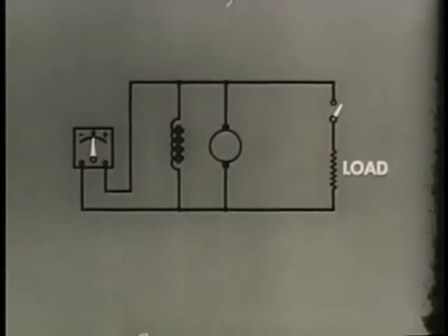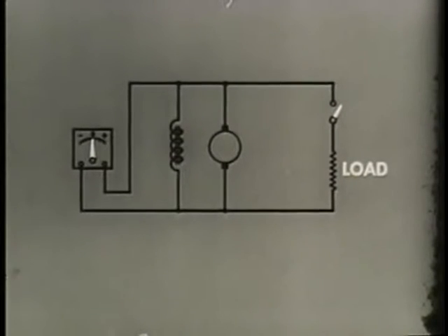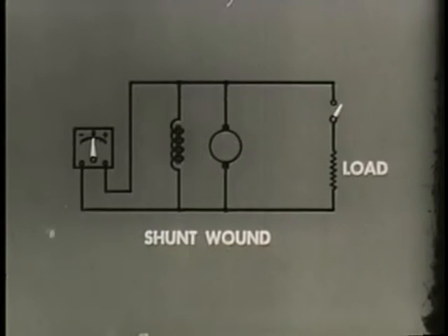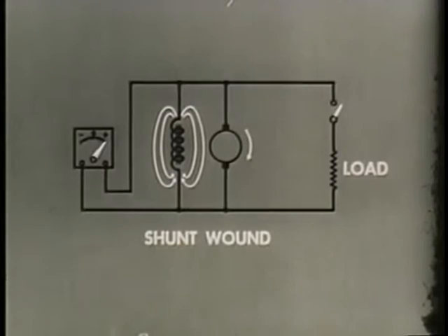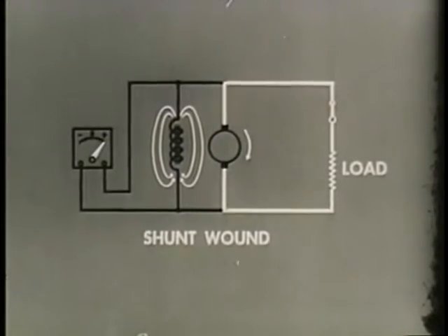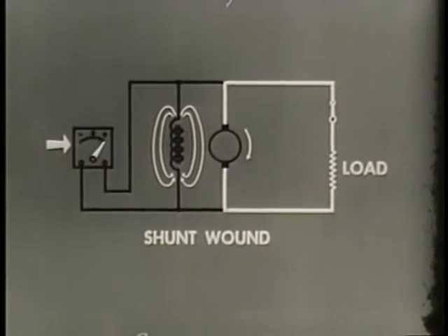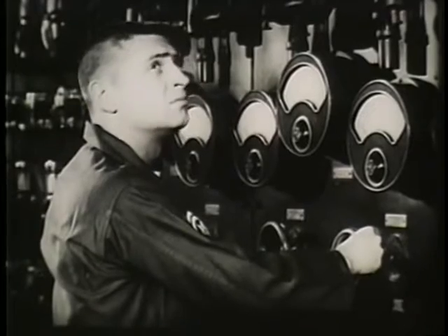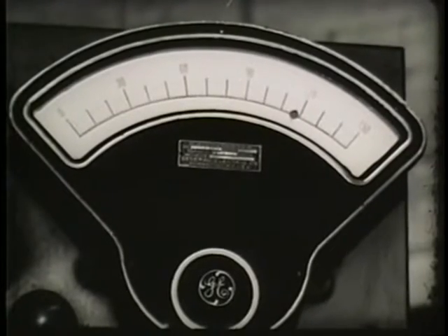When the field winding is connected in parallel with the armature and the load instead of in series, we have a shunt-wound generator. Now the field current is independent of the load current. Therefore, an increase in armature current will not cause an increase in the voltage output. Voltage regulation here is greatly improved. In shunt-wound generators, changing load causes relatively small change in voltage output.